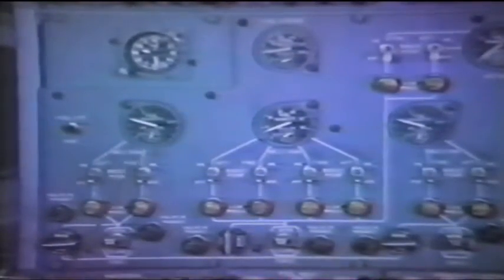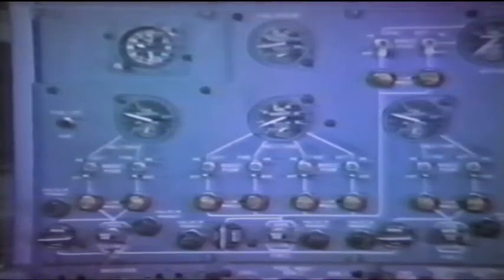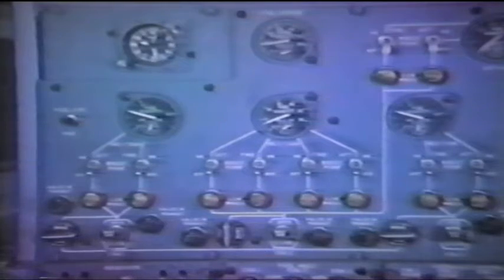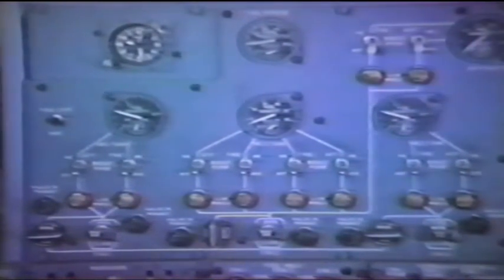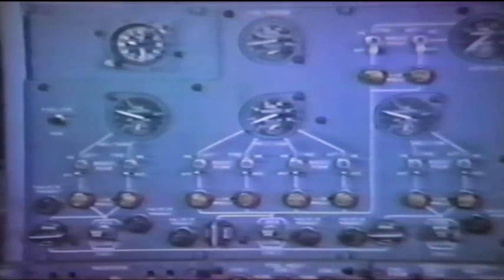Now, the output of the boost pumps can go through the engine fuel shutoff valve to the engine. Or it can go through a cross-feed valve to the fuel cross-feed manifold. And through that method, it could go through another cross-feed valve to any other engine. For example, if we opened up the number 1 cross-feed, if the number 2 boost pumps were inoperative, we could use the boost pumps in the number 1 tank to feed the number 1 engine, and through the cross-feed, provide fuel to the number 2 engine also. That's the best way we have. That's the only way we have, really, other than maladjusting the fuel flows, to balance up unequal fuel tank readings. So we can open a cross feed first, establish a flow of high pressure fuel, and then turn off the boost pumps in the tank that we do not want the fuel to burn down in, and we can equalize a fuel imbalance to some degree that way.